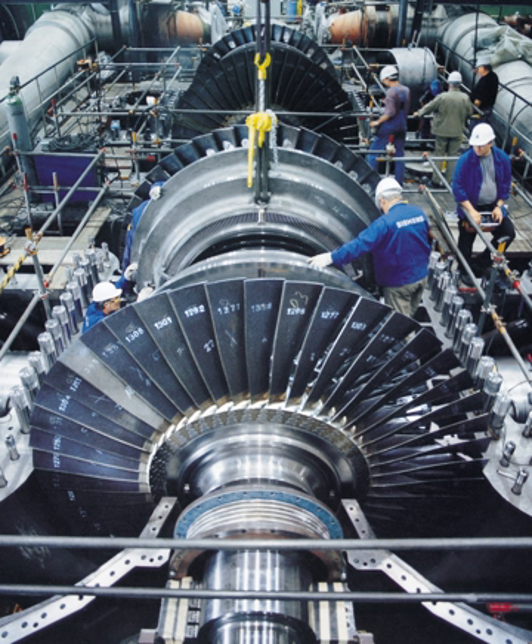The speed at which the rotor spins in combination with the number of generator poles determines the frequency of the alternating current produced by the generator. All generators on a single synchronous system, for example, the national grid, rotate at sub-multiples of the same speed and so generate electric current at the same frequency.